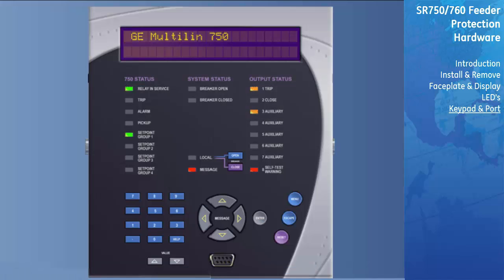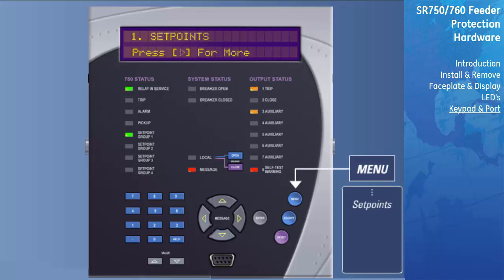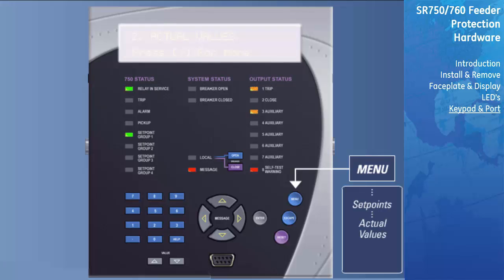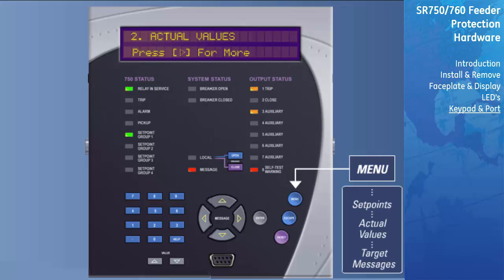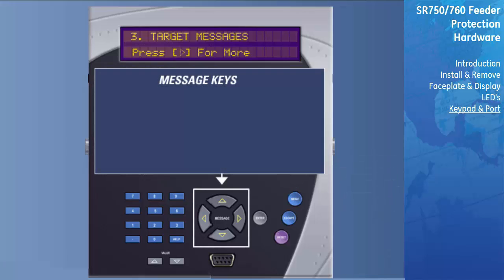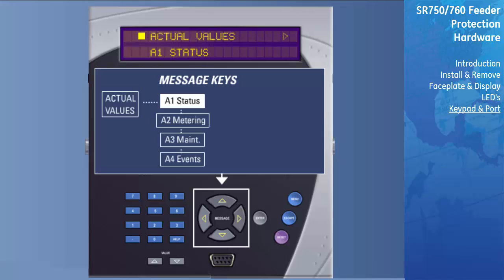The relay's messages are organized into pages under the main headings of Set Points, Actual Values, and Active Targets. The menu key is used to navigate through the main headings. Each page is broken down further into logical subgroups of messages. The message keys may be used to navigate through the subgroups. For example, when the menu key has been used to select the Actual Value main page, pressing the Message Right key will move you into the A1 Status menu.